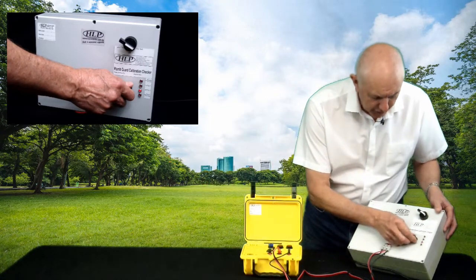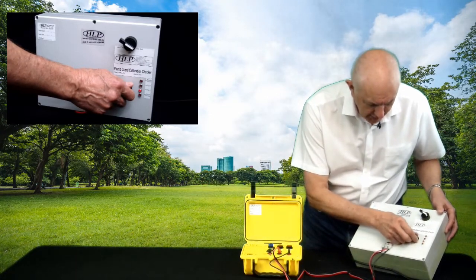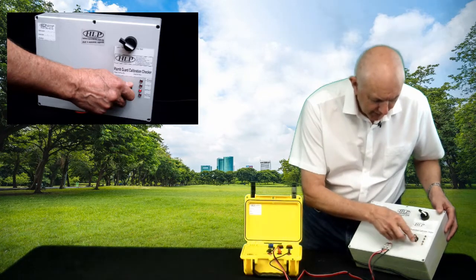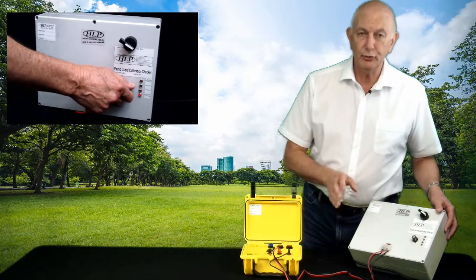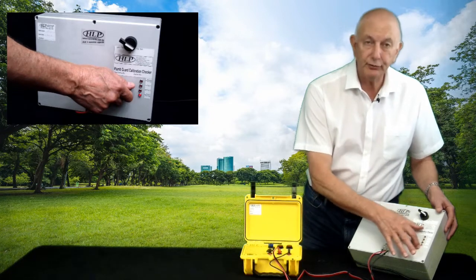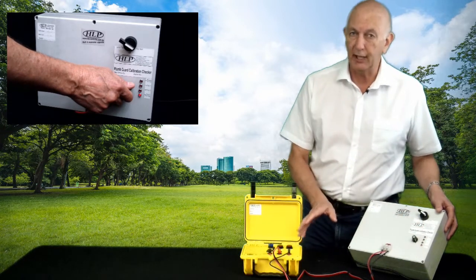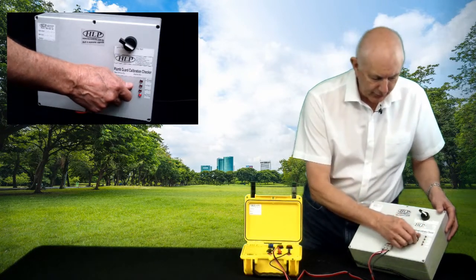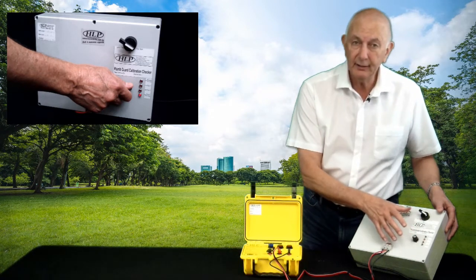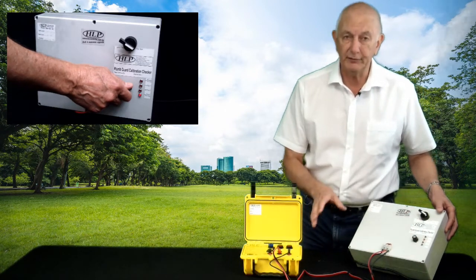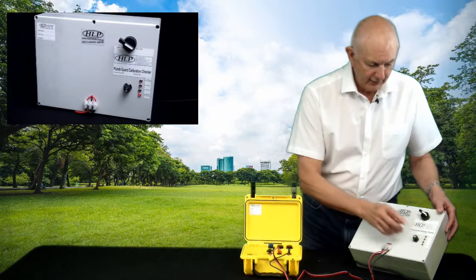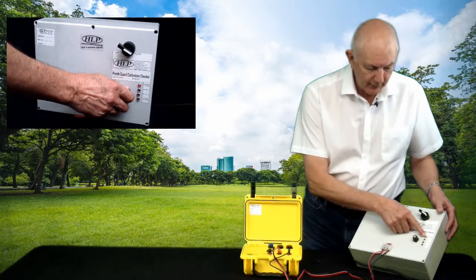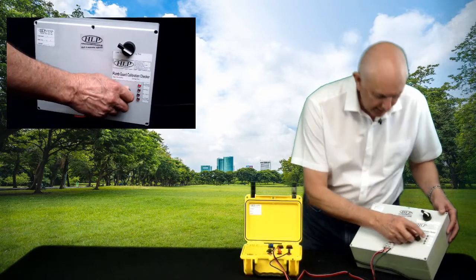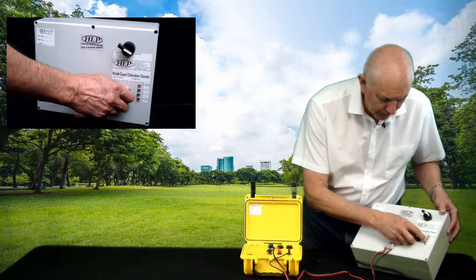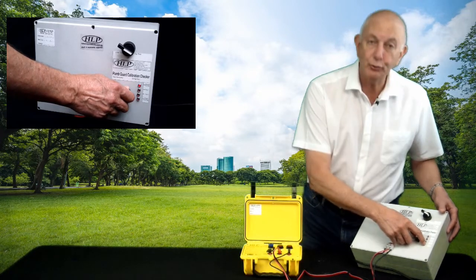So there's another switch setting, which is the 3rd. So if the Plumb Guard doesn't trip in any of those 3 settings, then it's faulty. You can't use it. If the Plumb Guard trips in any of the 3 settings, then it's okay and it's still within its specifications. So just to clarify again, you've got 3 switch settings. The indicator says trip 1, trip 2, and fault if no trip.